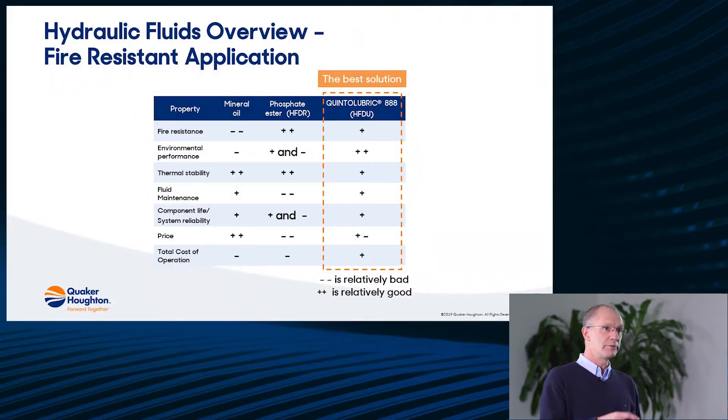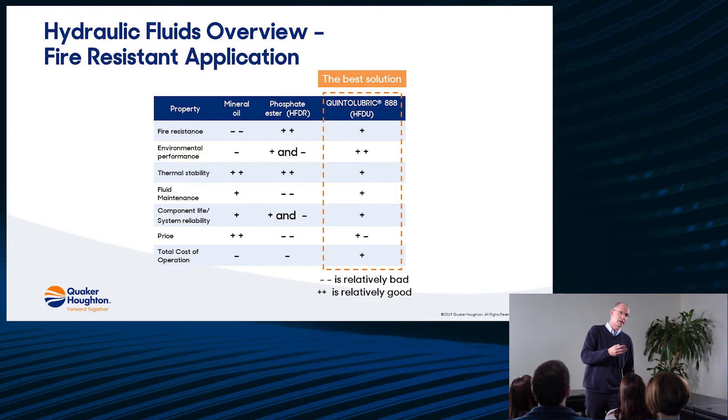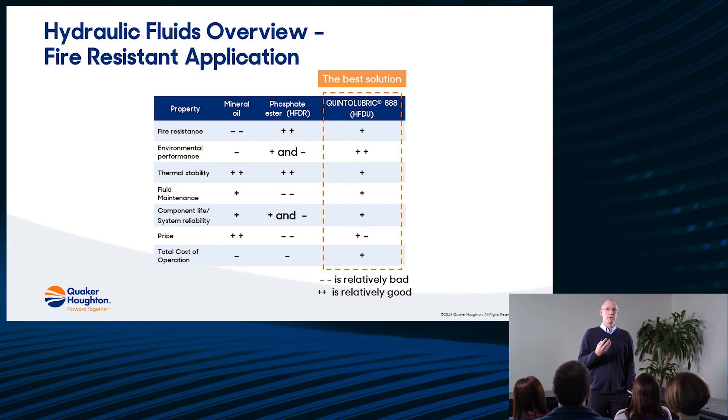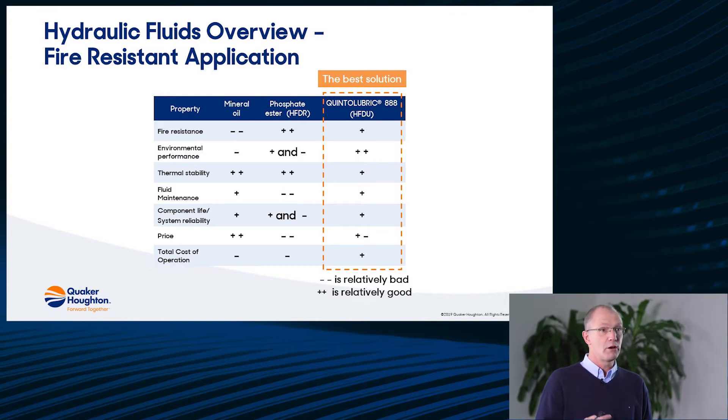If you compare phosphate esters and Quintolubric 888, phosphate esters are good in fire resistance by itself, but they score less on environmental performance simply because they are sensitive for CMR — carcinogenic, mutagenic, reproductive. Thermal stability is good, but fluid maintenance needs a lot of attention because of the aging of phosphate esters: when they age they produce aggressive by-products.